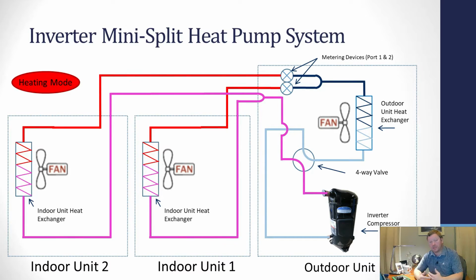Now, depending on the size of the units, depending on your conditions, this might only overshoot by 1 degree and you might not even notice the difference. However, it's very common that bedroom indoor units are oversized. It just happens. And so what ends up happening is now you've got a unit inside the bedroom that's calling for more than it really needs. The compressor doesn't ramp down quite enough, and that living room unit then overshoots beyond what's comfortable.